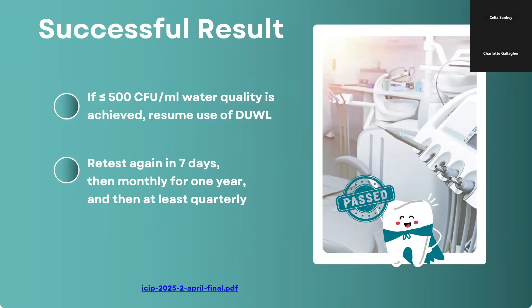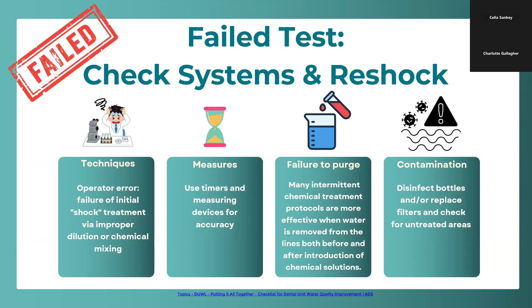If the test indicates a failed result of greater than 500 CFUs, all components of the system should be evaluated. It could also be a problem of technique or operator error related to improper dilution or chemical mixing. You must check measures of time or measuring devices. Failing to purge or empty lines fully will cause product dilution by water. The lines may also persist with higher microbial levels if contaminated filters were left on, water bottles were contaminated, or if any lines were not completely exposed to the shock or treatment product. After troubleshooting, reshock and test again until the required water quality is met.